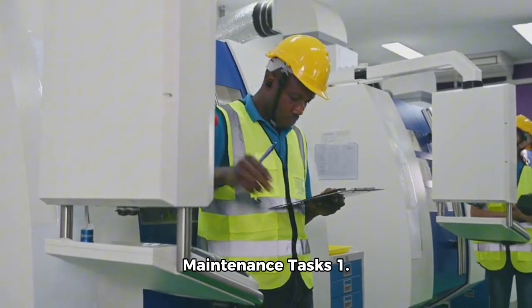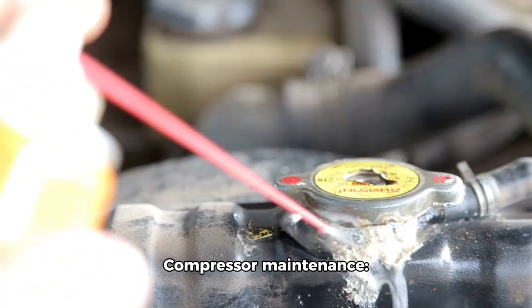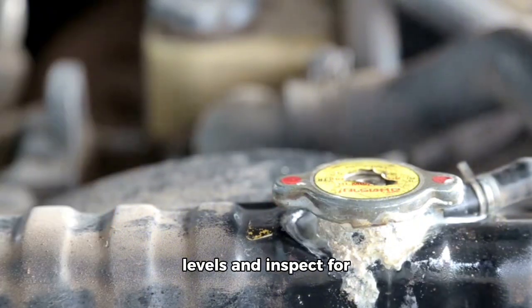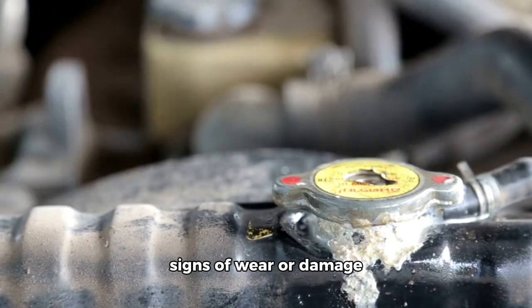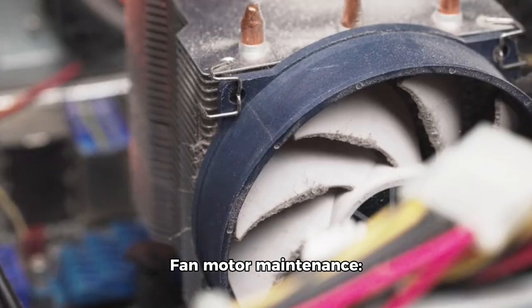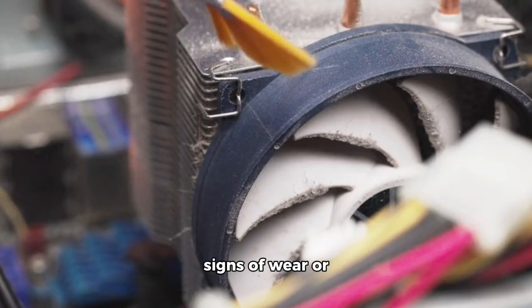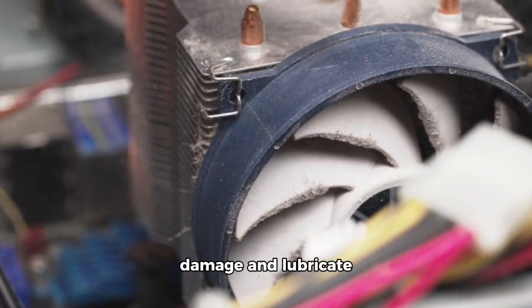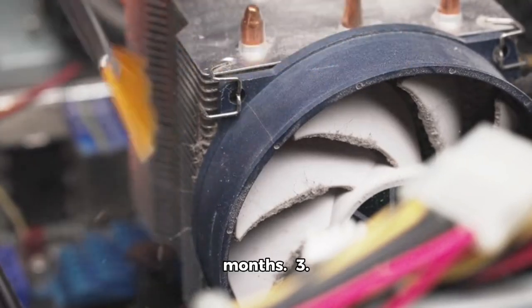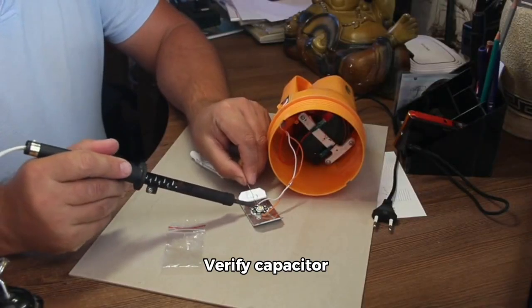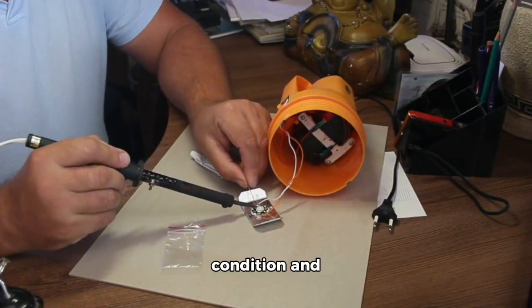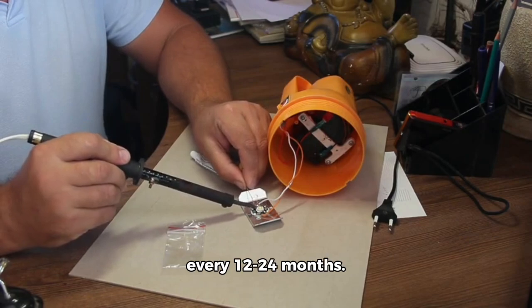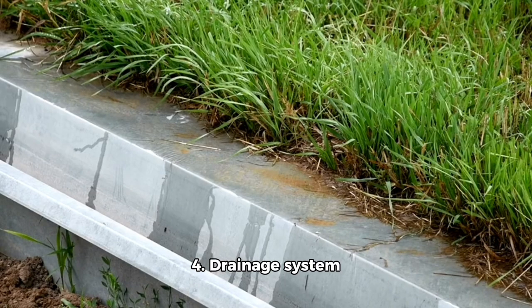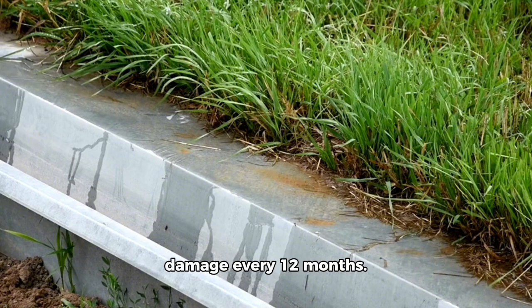Additional maintenance tasks. 1. Compressor maintenance. Check compressor oil levels and inspect for signs of wear or damage every 12 months. 2. Fan motor maintenance. Inspect fan motors for signs of wear or damage and lubricate as necessary every 12 months. 3. Capacitor checks. Verify capacitor condition and replace if necessary every 12 to 24 months. 4. Drainage system checks. Inspect drainage systems to ensure proper water flow and prevent water damage every 12 months.